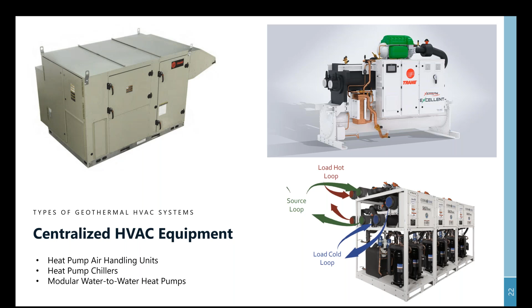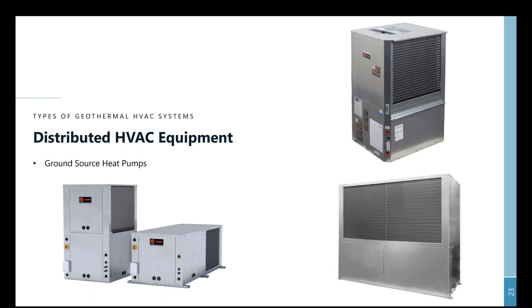Another approach is the use of distributed HVAC equipment. This is effectively either vertical or horizontal ground source heat pump units, and these would be distributed throughout the building. Oftentimes you would see this type of application in, say, a multifamily building or potentially a school building, where you have individual heat pump units in every zone throughout the building, and you're taking the fluid through the ground loop heat exchanger and then pumping that directly to equipment that is distributed throughout the building. Again, both the centralized and distributed HVAC equipment applications can be suitable. It really just depends what the specifics are for your particular project to know which system is going to be the right one to use.